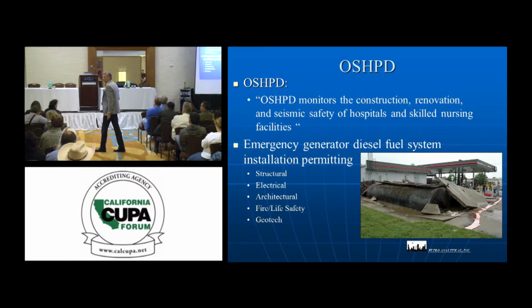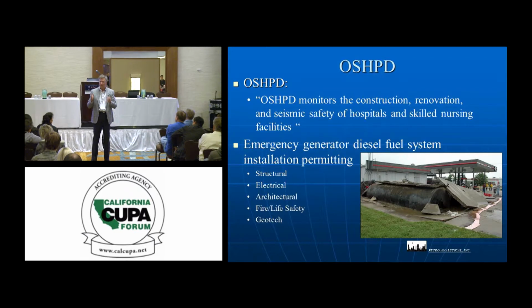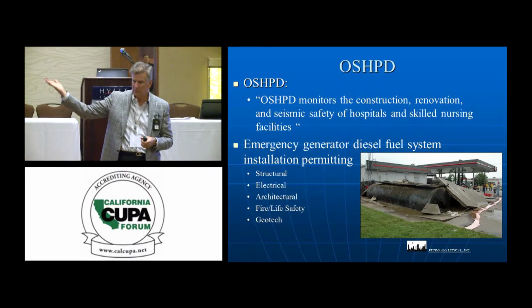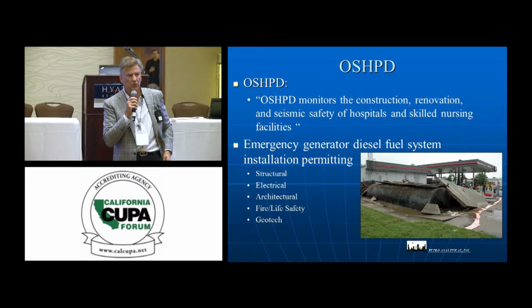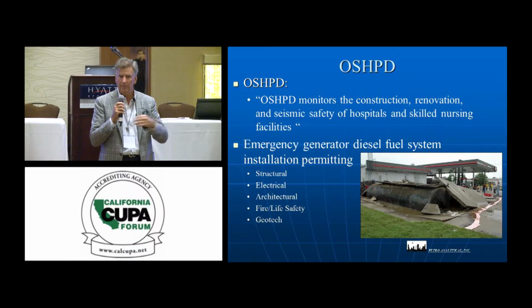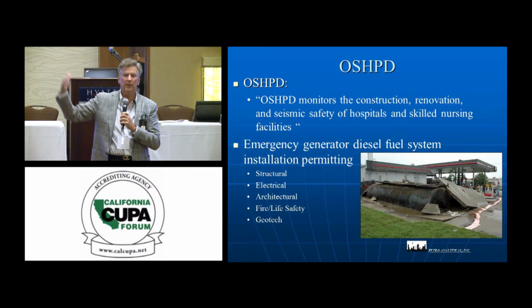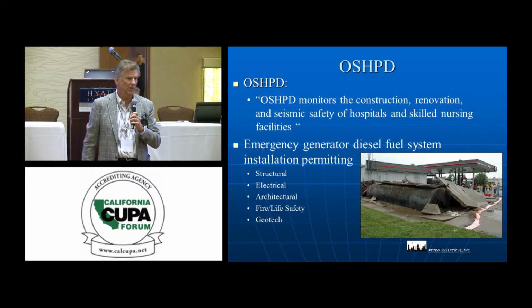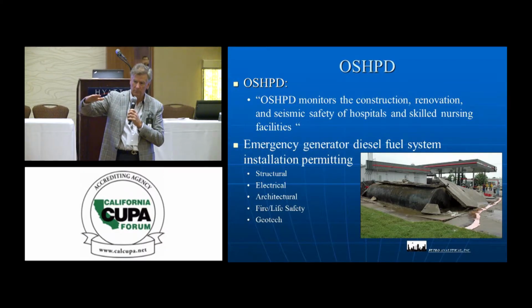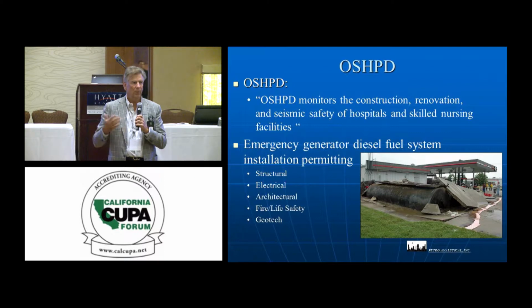Okay. So the question is, if you're feeding a boiler system and a generator system, you got a number of considerations. First of all, the generators are required to have a minimum 72 hours runtime. So you do a straight calculation of generator consumption at full rated load. We need to make a decision on fuel capacity for the generators first. So with a 72-hour runtime minimum, we do that calculation. If there's enough room left over in a single tank, obviously the owner would want to feed the boilers off that single tank rather than buy a separate tank. I mean, that's pretty obvious. So we would limit the drop tube in that tank so the boiler pickup could not get down into the generator fuel. That doesn't address the regulatory issue, but it's normally what they want to do.